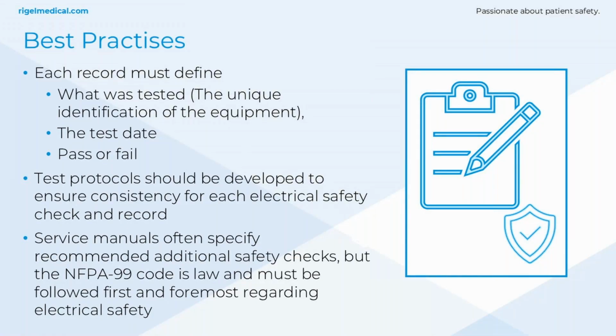So some of the best practices are defined in NFPA 99, and this is important when talking about a product like the SafeTest 60 Plus because it's a manual safety tester. It doesn't record results. There's no data export like some of our other safety analyzers or some of the other safety analyzers out there. Some people still choose to use these types of analyzers because they're simple and effective for biomed, and NFPA states the minimal standard of documentation required for routine checks of equipment.